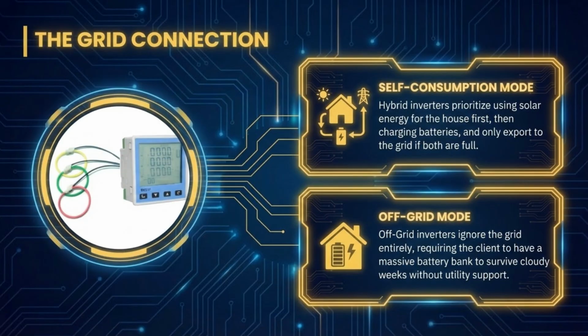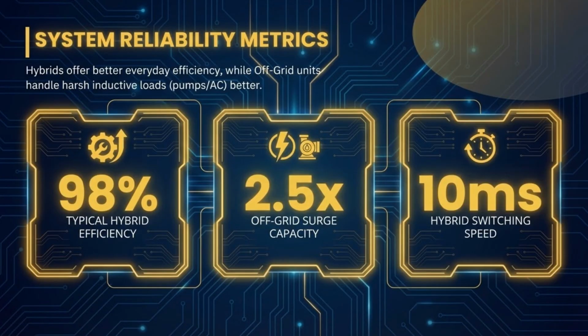Off-grid inverters ignore the grid entirely, requiring larger battery banks for extended autonomy. System reliability metrics show hybrid efficiency at about 98% with a 10 millisecond switching speed. Off-grid units offer superior surge capacity, roughly 2.5 times better for inductive loads.